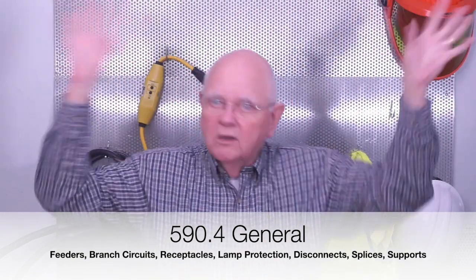Now, the next section that the NEC gets into in Article 590 is going to talk about some different general information about, for instance, installation and wiring methods that I can use. So, for instance, it tells us that for these temporary installations, I can use, up to any height, type NM cable. What you and I call it, Southwire's trademark trade name, is Romex. So we install this Romex, don't we? You see that a lot for temporary lighting in buildings.